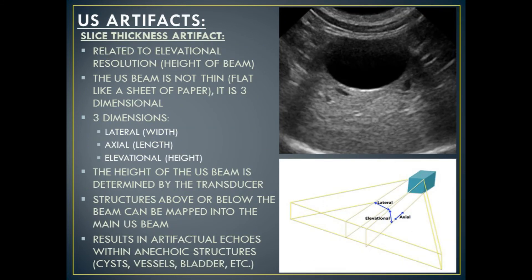Slice thickness artifact is related to elevational resolution, which is the height of the ultrasound beam. The ultrasound beam is not thin or flat like a sheet of paper — it has three dimensions: the lateral dimension (the width), the axial dimension (the length), and the elevational dimension (the height). The height of the ultrasound beam is determined by the transducer. Structures above or below the beam can be mapped into the main ultrasound beam, resulting in artifactual echoes within anechoic structures such as cysts, vessels, and the bladder.